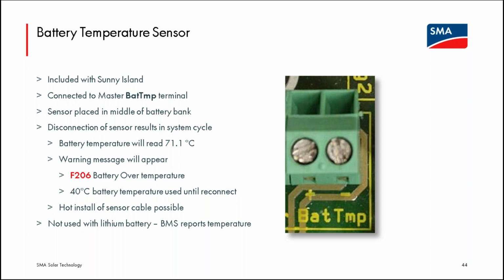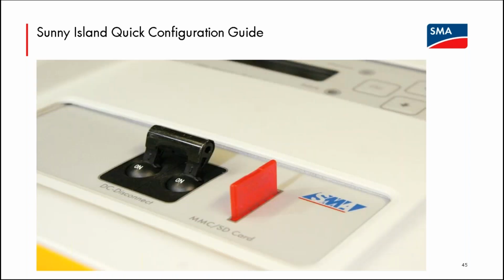For the lithium-ion batteries, the communication cable from the battery management system to the Sunny Island will bring in that temperature information. So it is only needed for the lead acid battery banks, and you only wire the temperature sensor from the master to the bank, even if there are multiple Sunny Islands.